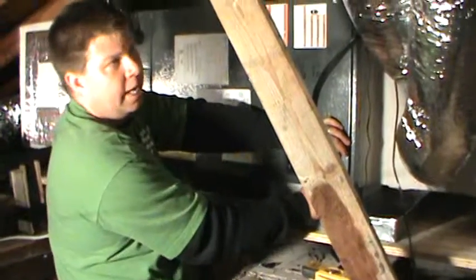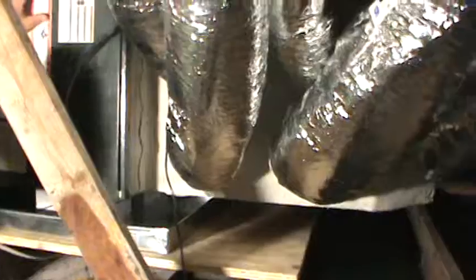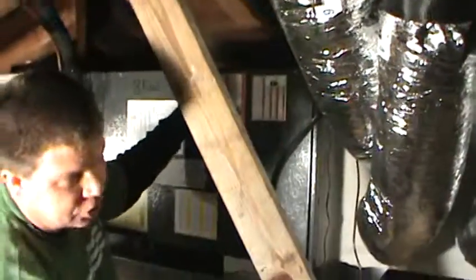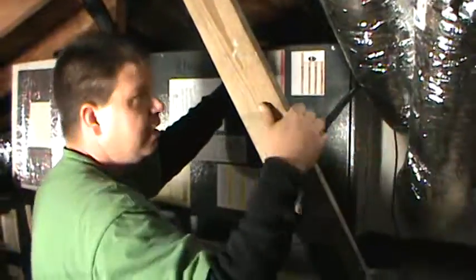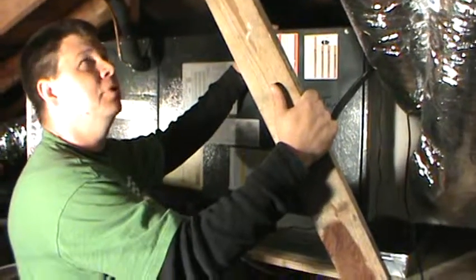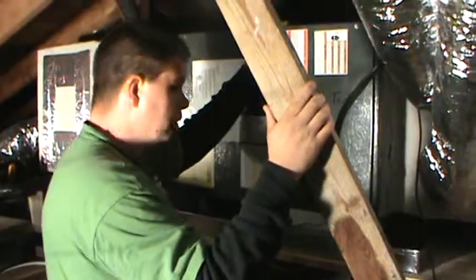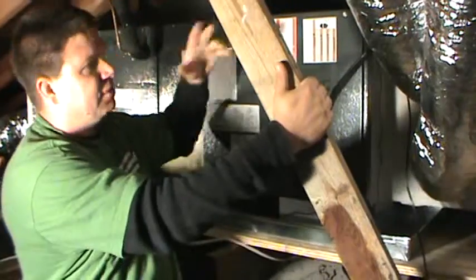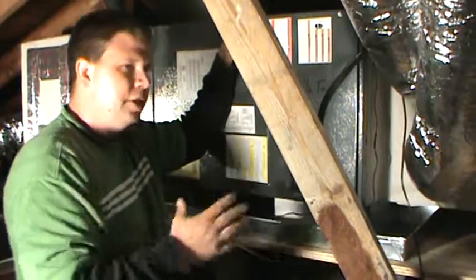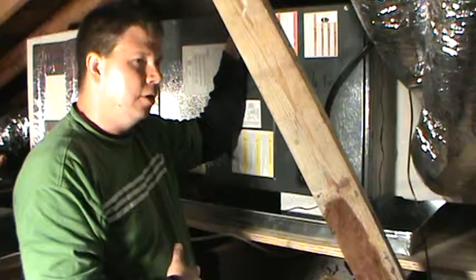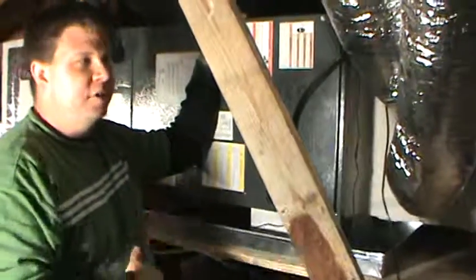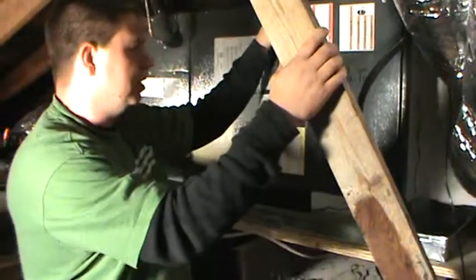You're up here, you're going to want to go ahead and check your ductwork. You want to look and make sure that you don't have any loose connections at the plenum. You want to make sure you don't have any kinks, no tears, no rodents tearing into any ductwork. Of course, check your return. Just kind of look down the lines and see that it's all in good shape. If not, let the customer know, you have some ductwork. Even if it's in fair condition, even if it's a little older, it's not torn or anything, but just let them know the condition in which the ductwork's in.